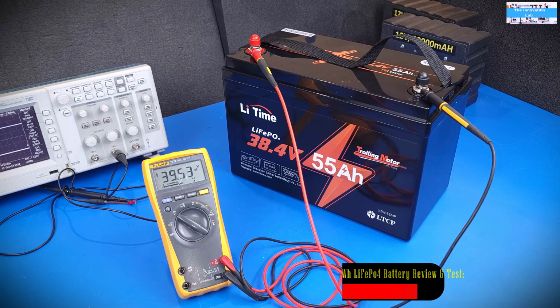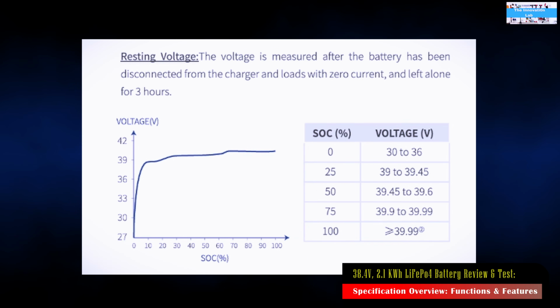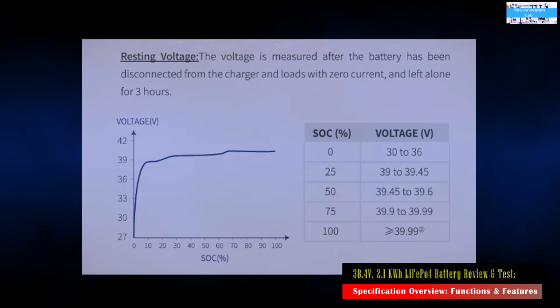This is a plot of voltage against SOC percentage as provided in the table to the right. At 0 SOC, the battery voltage should be about 30 to 36 volts, and at 25% SOC, the battery voltage should be about 39 to 39.45 volts. If you take it all the way to 100% SOC, when the battery is fully charged, the voltage you should be measuring should be greater than or equal to 39.99 volts.